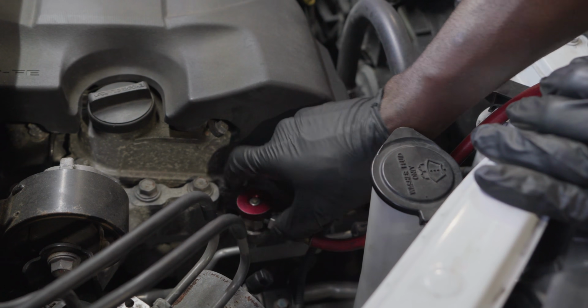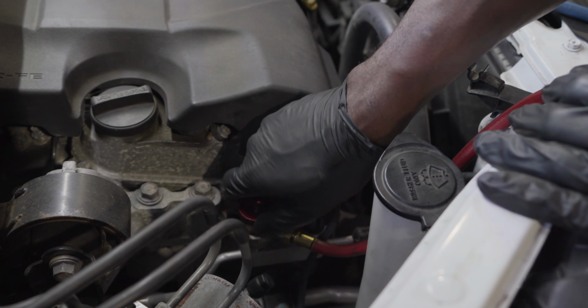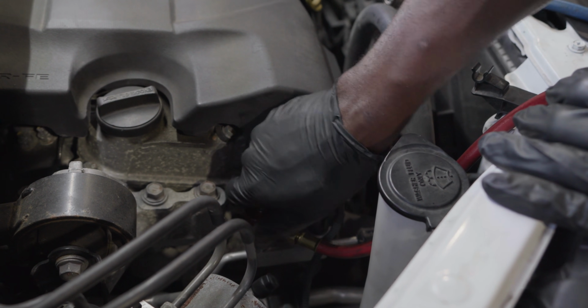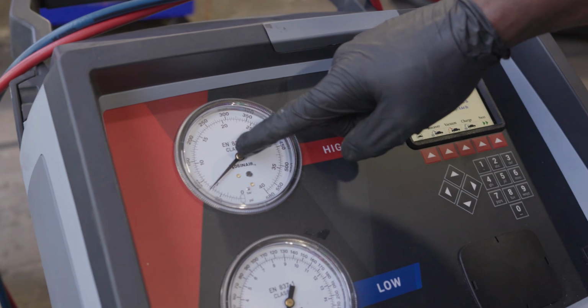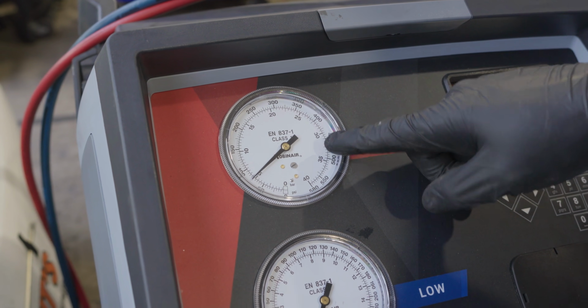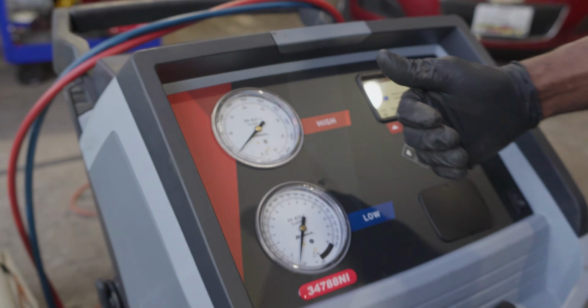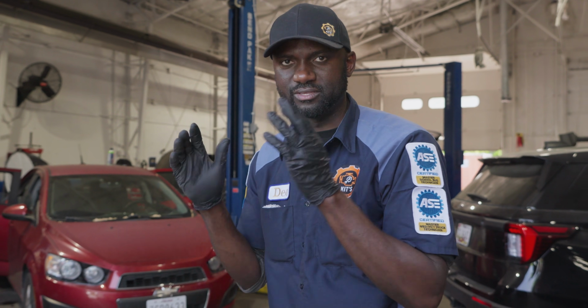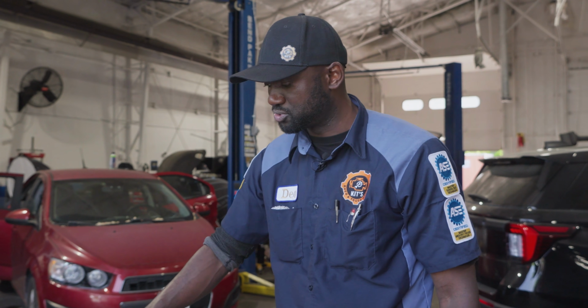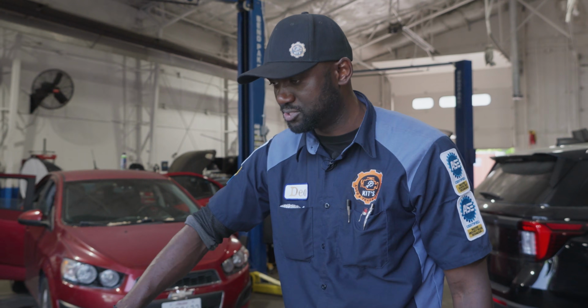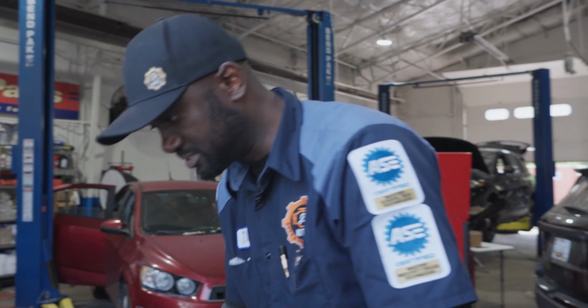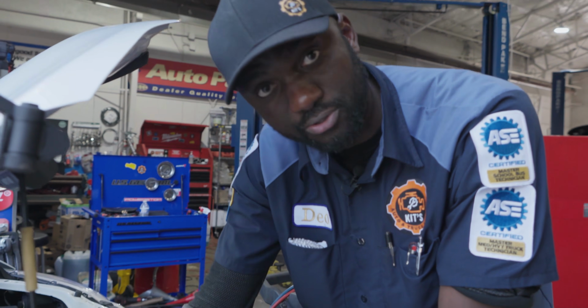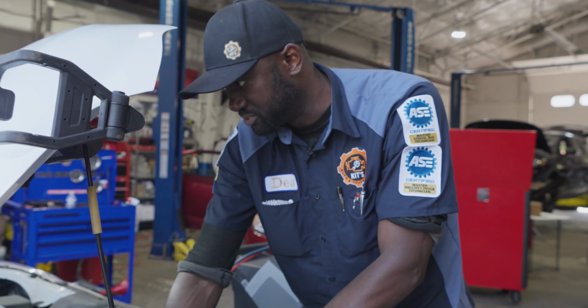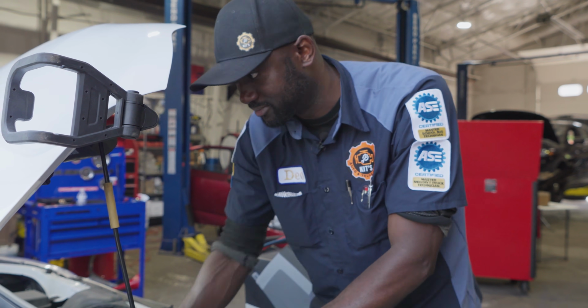Okay, so we got this connected. I'm going to turn on the knob. I can hear refrigerant flowing through. Now let's look at this gauge - you see how it went up? This tells me there's refrigerant in the system, so our AC system is not leaking. Because if the system was leaking, this gauge would be stuck at 0. The fact that the gauge moved means our system is holding refrigerant, so that's a good thing already. We're most likely not dealing with a leak here.